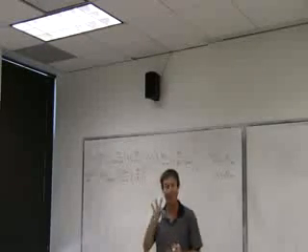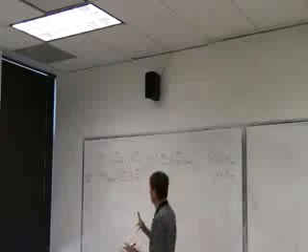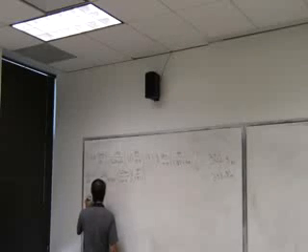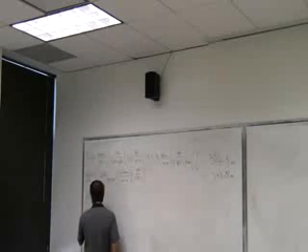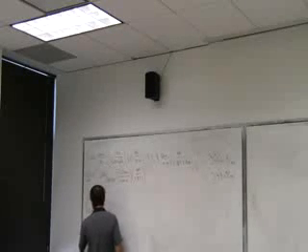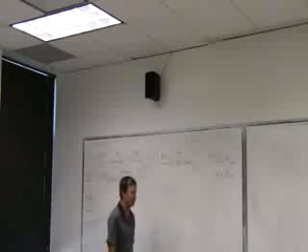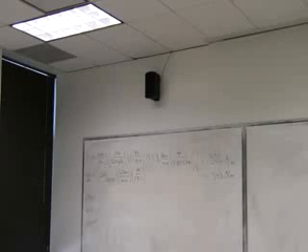Now the other three have to do with the pressures. We had 3 pressures. We had the 28 psi with the gauge. We had the 22 psi with the gauge. And we had 28.844 millivolts coming out of the pressure transducer. And we can go walk over and see if I can actually read any of that. It's over there. Oh my gosh, it's small. You get it.